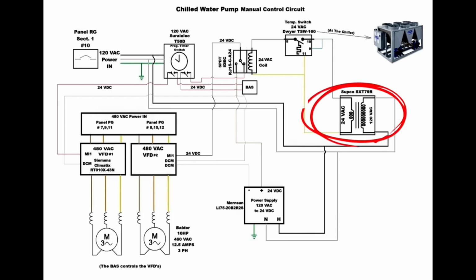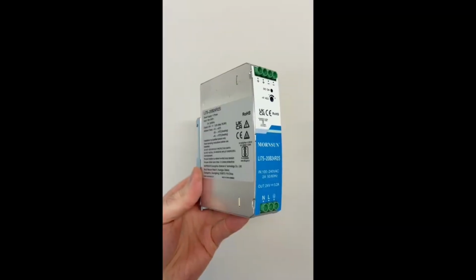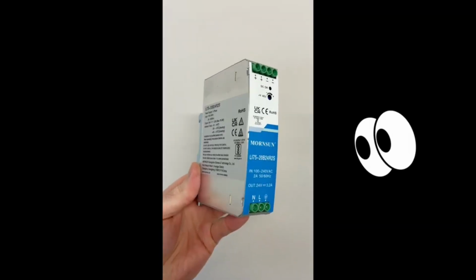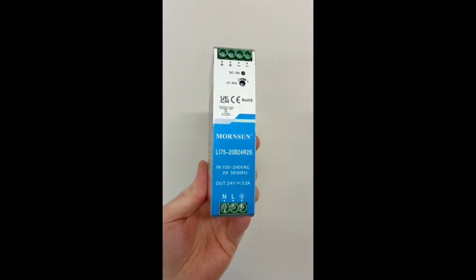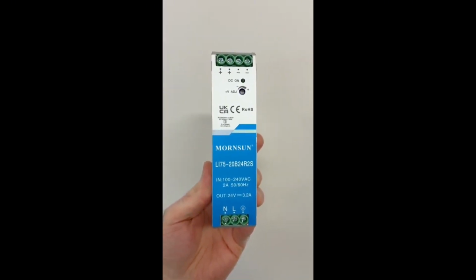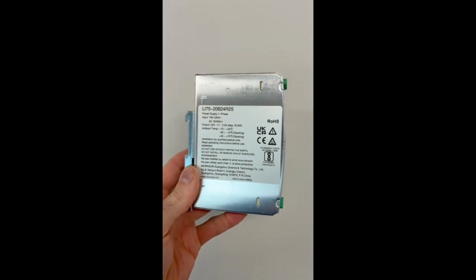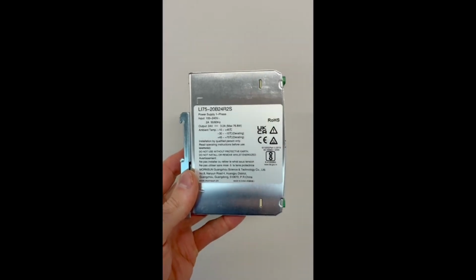The step-down transformer, that's taking 120 volts, stepping it down to 24 volts to operate the temp switch up at the chiller. And the programmable digital timer operates on 120 volts. So just wanted to clarify that. And so here's a close-up view of the power supply. So you got 120 volts coming in on the bottom, 24 volts DC coming out the top. Here's the specs for it.